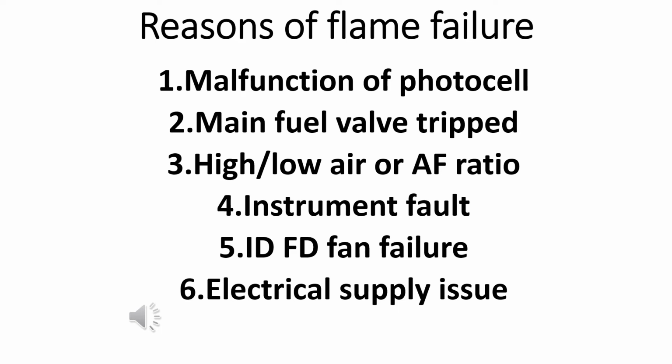ID fan most commonly trips due to damaged bearing. And because the ID fan is mounted on the chimney on the exhaust flue gases, due to high temperature their bearing becomes damaged.